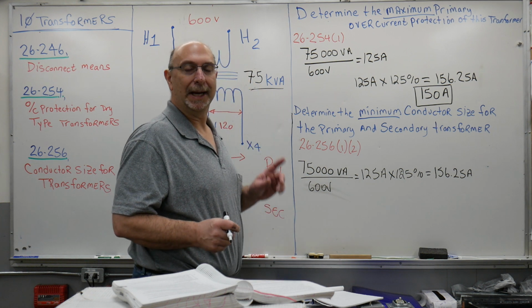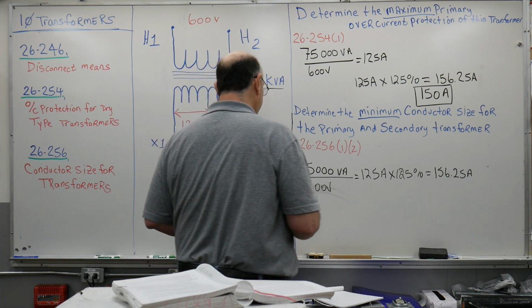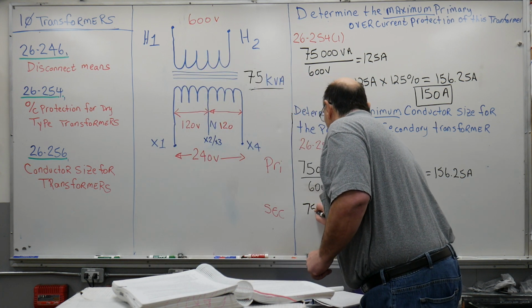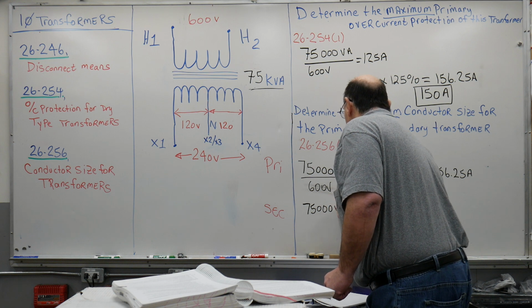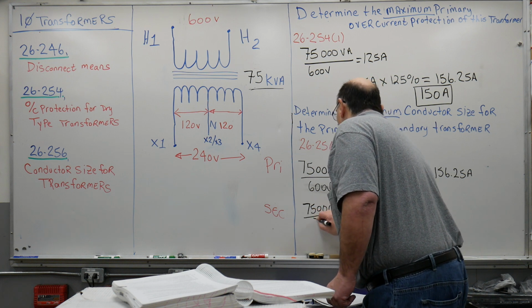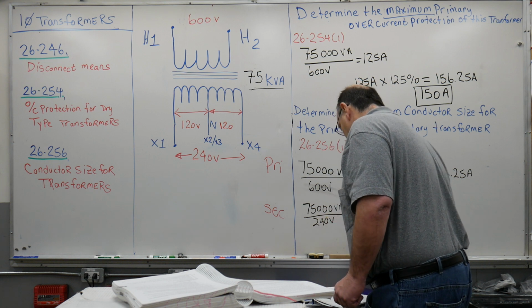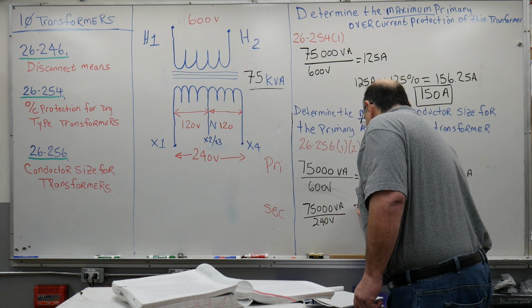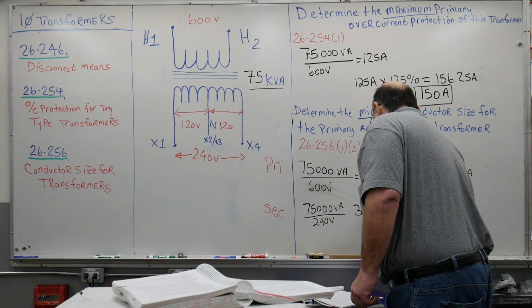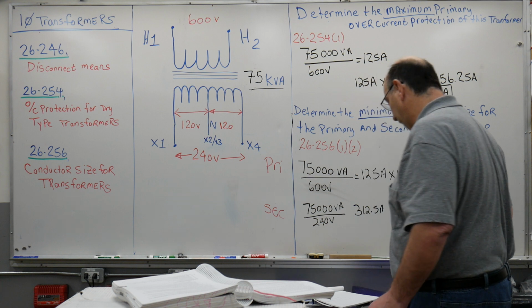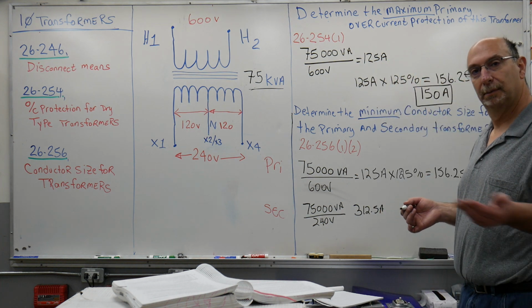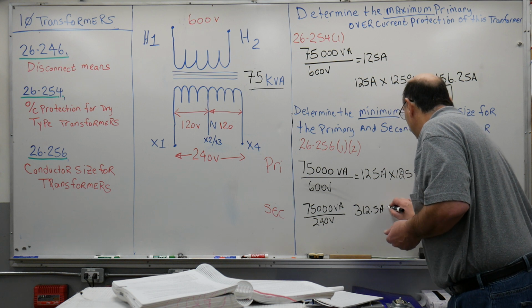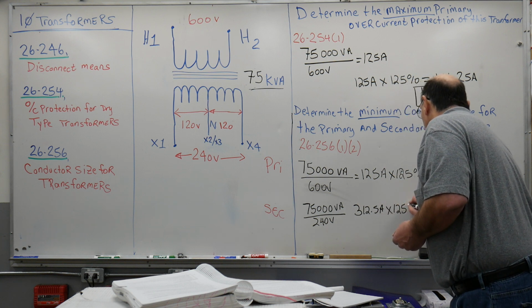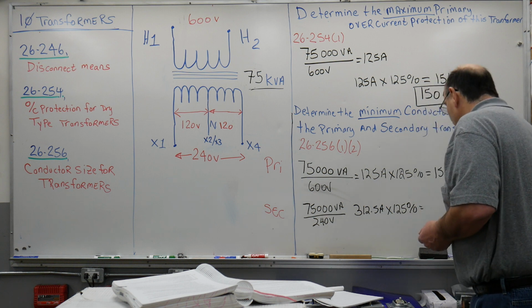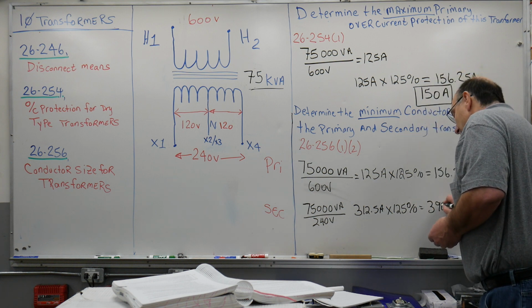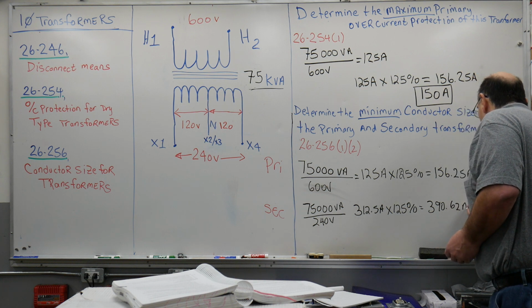Next, we're going to work on the secondary conductor ampacity. Now, 75,000 VA divided by 240 volts. And what do you come up with? Roughly 312.5 amps. Now what do we have to do with this? Multiply by 125%. And we come up with a grand total of 390.62 amps.